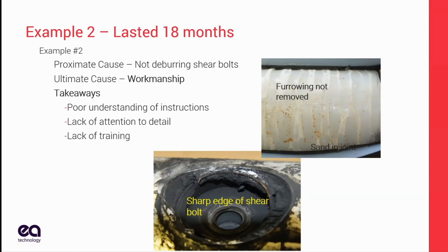But if you didn't know that you had to have a perfectly smooth installation, and you didn't know that a little bit of sand like this could be a problem, you would think you did a good job. And here we are 18 months later fixing the cable.